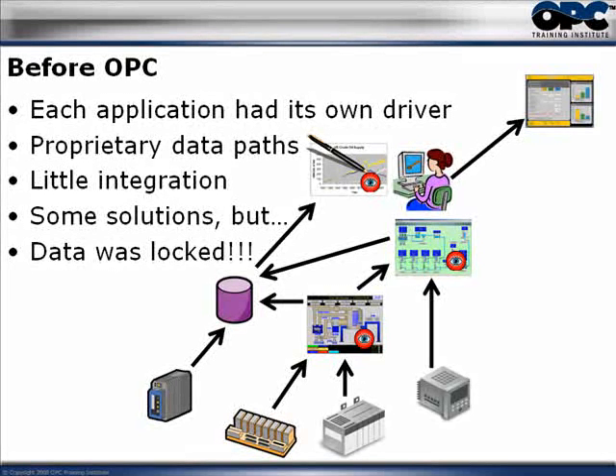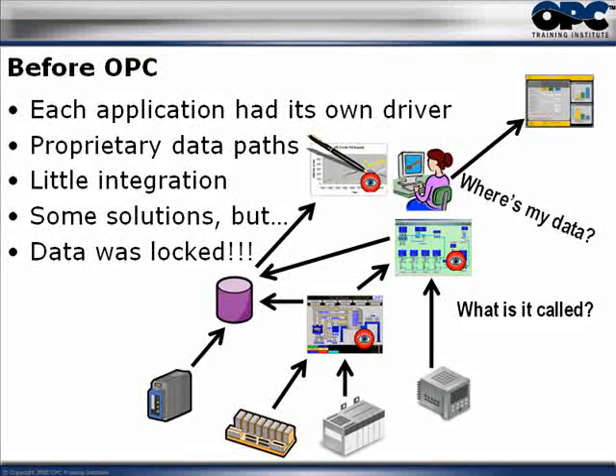Here is the source of the problem. Number one: where is my data? If I have data on a tank inside my refinery, what PLC do I get it from, what control system, and what is it called? Different PLCs may use different naming conventions. Number two: what happens when there are changes? When there's a change in one PLC, how does that change propagate from the PLC to the HMI, to the historian, to the ERP, to the CMMS?